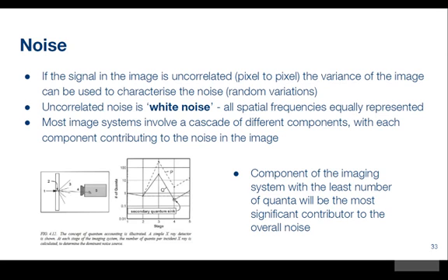This point 4 here is the capture of the optical photons. The reason we lose a lot of signal here is because the optical photons that are produced are just thrown out in all directions, and then we have a very small solid angle. So to increase the number of quanta that we actually detect at this stage 4, we can either increase the area of this camera system, or we could have some alternative way that's right up against it and is going to capture more of those optical photons.